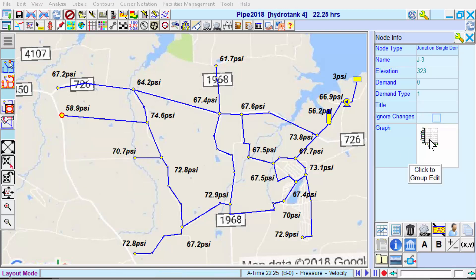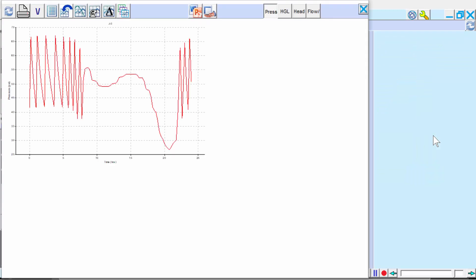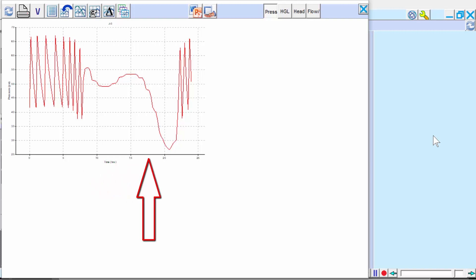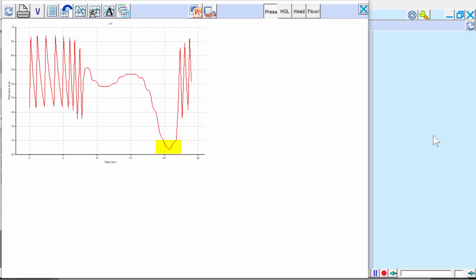Looking at the pressure results for node J3, we see that the pump kicks on continuously, approximately between hours 9 and 23. Also, system pressures fall below the minimum requirement.